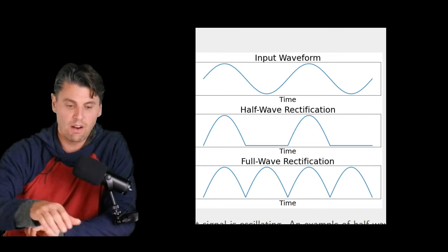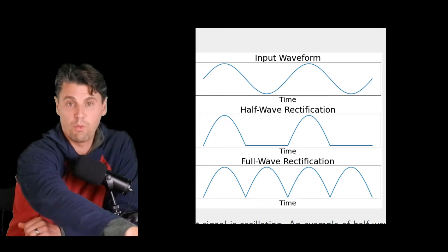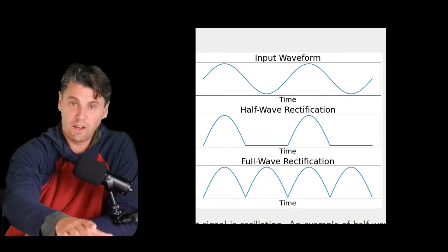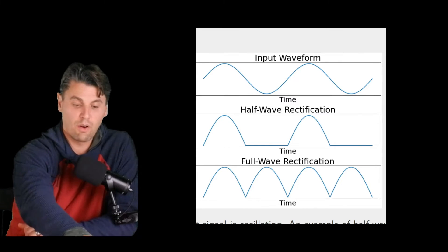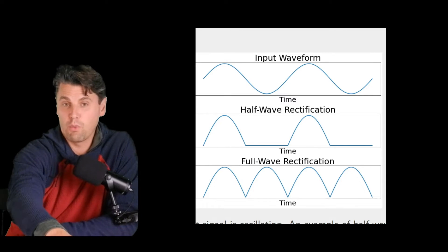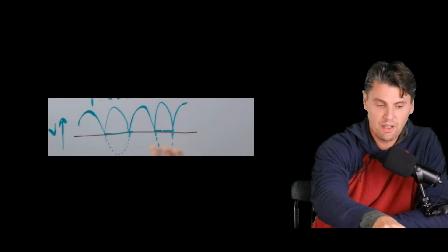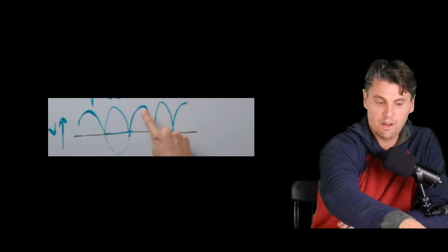When we define heat units later on, this is actually going to come into play again because this type of full wave rectification was done in the early days of x-ray. So a lot of the units actually are related to this type of full wave rectification. You can see that even with this full wave rectification, there's a lot of up and down in our signal here.